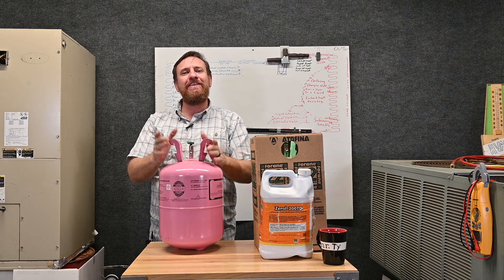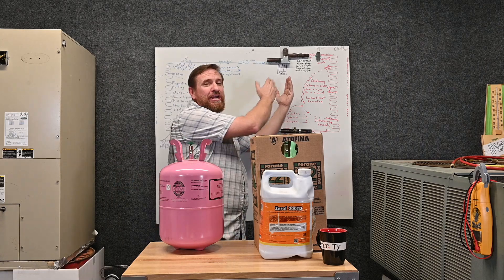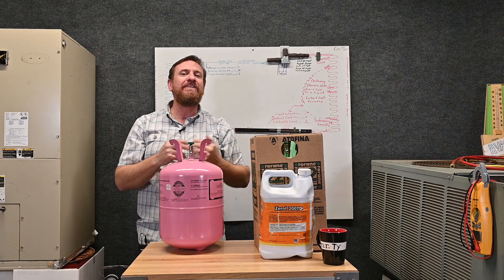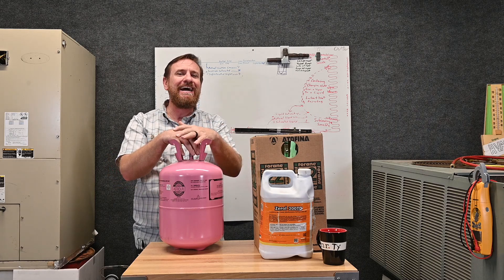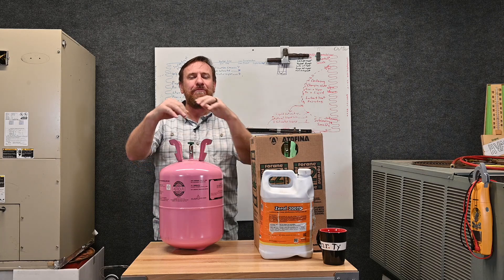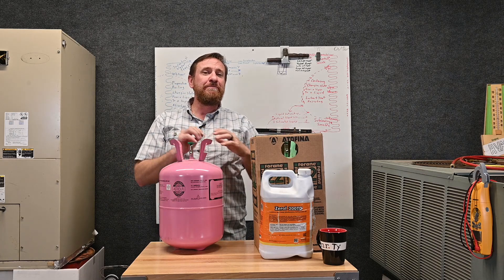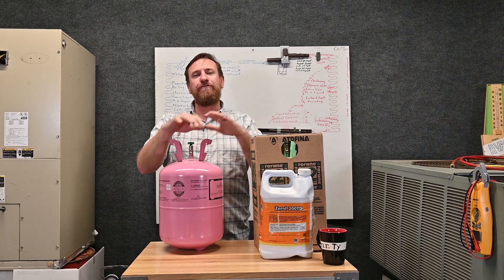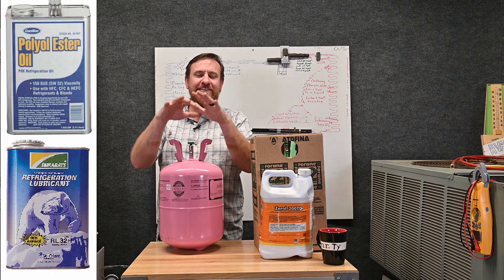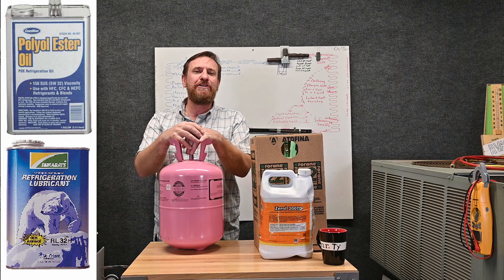This refrigerant works at a higher pressure. The compression ratio on two identically designed systems will be the same, but R-410A has a higher pressure. If the system is designed with brazes that aren't able to handle that higher pressure, there are going to be more leaks. So when changing from R-22 to R-410A, we have to replace the system for a R-410A system and use the POE polyol ester oil.